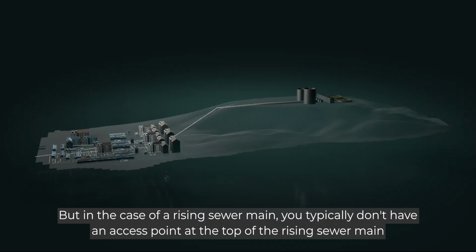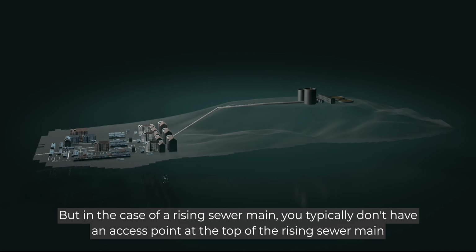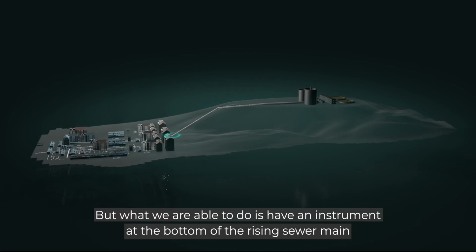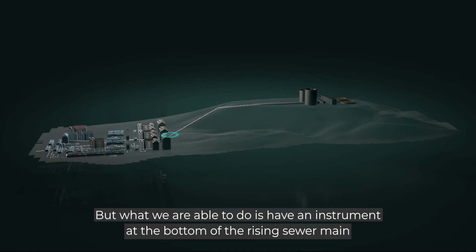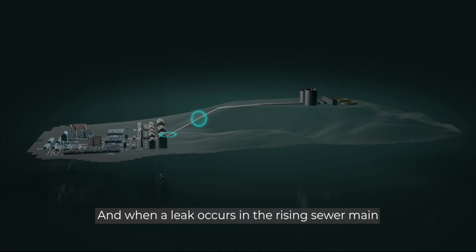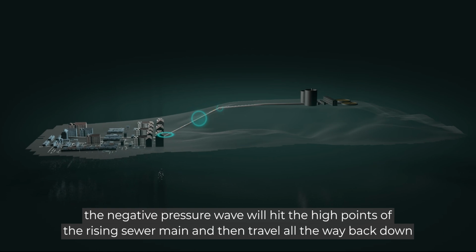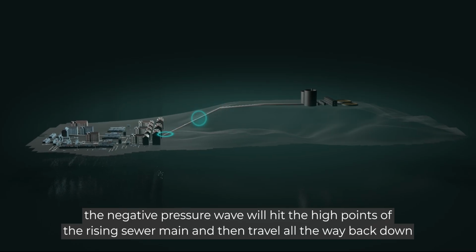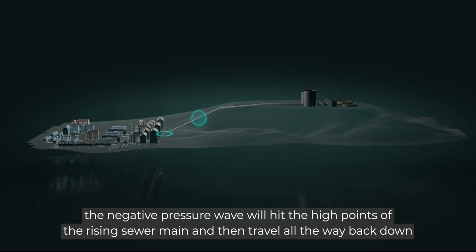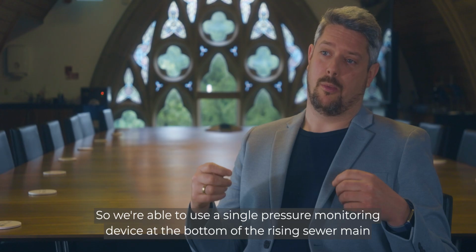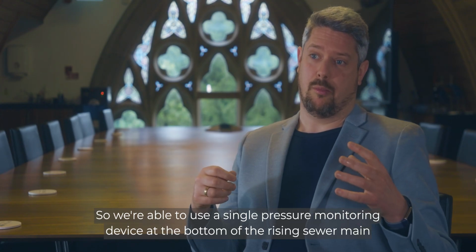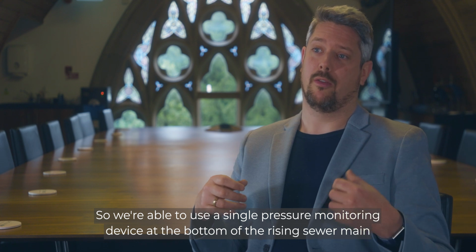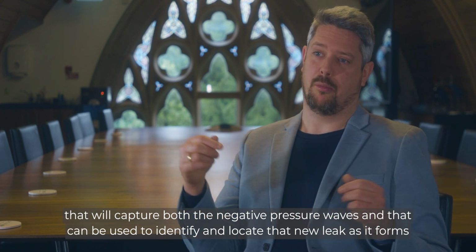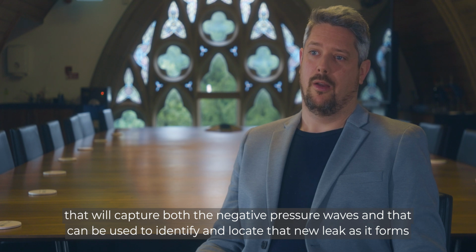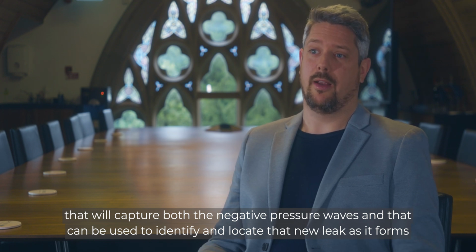But in the case of a rising sewer main, you typically don't have an access point at the top of the rising sewer main, but what we are able to do is have an instrument at the bottom of the rising sewer main, and when a leak occurs in the rising sewer main, the negative pressure wave will hit the high point of the rising sewer main and then travel all the way back down. So we are able to use a single pressure monitoring device at the bottom of the rising sewer main that will capture both the negative pressure waves, and that can be used to identify and locate that new leak as it forms.